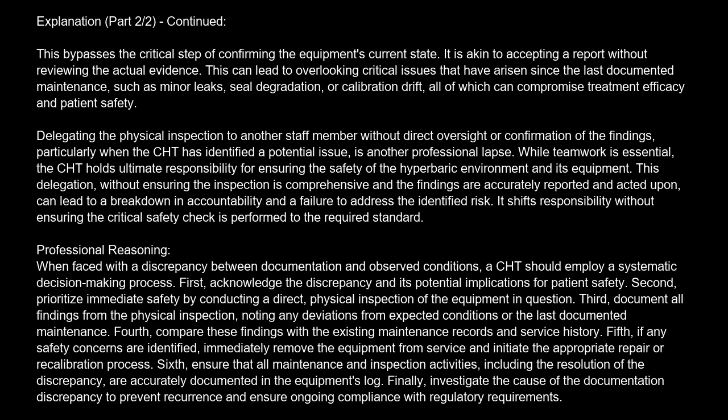Fifth, if any safety concerns are identified, immediately remove the equipment from service and initiate the appropriate repair or recalibration process. Sixth, ensure that all maintenance and inspection activities, including the resolution of the discrepancy, are accurately documented in the equipment's log. Finally, investigate the cause of the documentation discrepancy to prevent recurrence and ensure ongoing compliance with regulatory requirements.